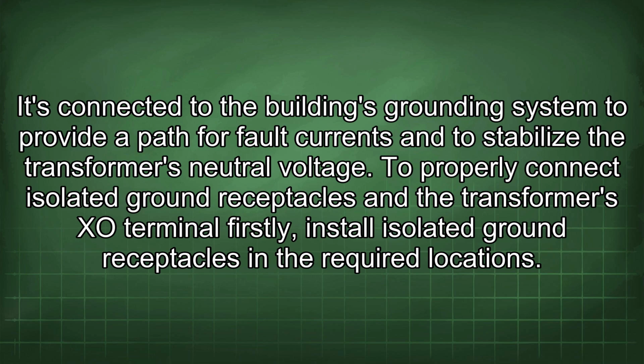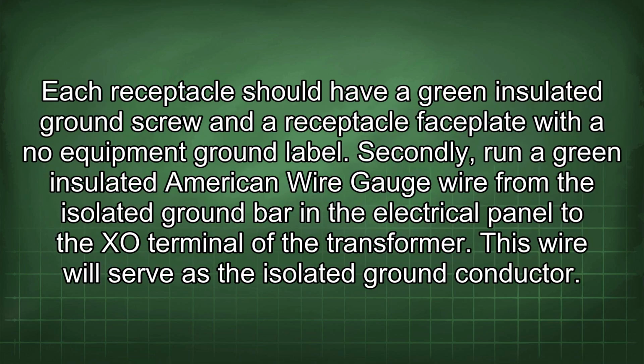voltage. To properly connect isolated ground receptacles and the transformer's XO terminal, firstly, install isolated ground receptacles in the required locations. Each receptacle should have a green insulated ground screw and a receptacle faceplate with a no equipment ground label. Secondly, run a green insulated American wire gauge wire from the isolated ground bar in the electrical panel to the XO terminal of the transformer. This wire will serve as the isolated ground conductor.